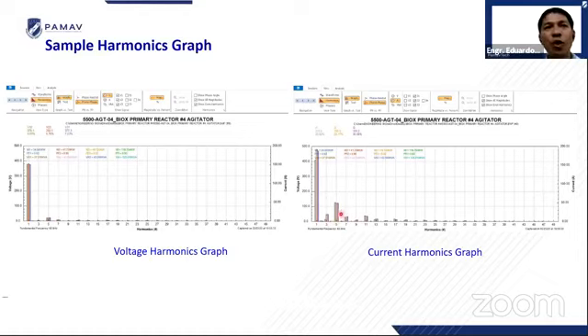See here, almost 150, it's so high, okay? That's why there's an effect in the voltage. See the 5 and 7 here, okay? So in most plants, the problem is the VFD. That's why we have to mitigate. How can we mitigate those harmonics?